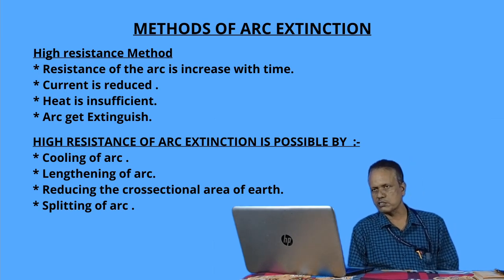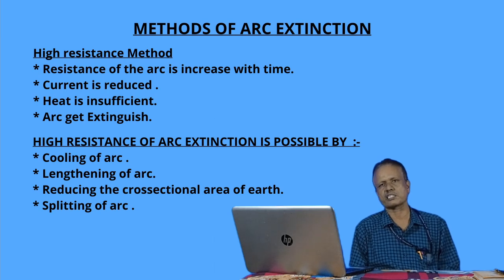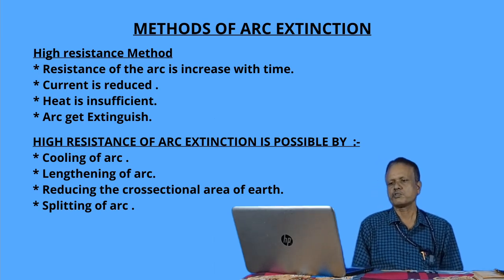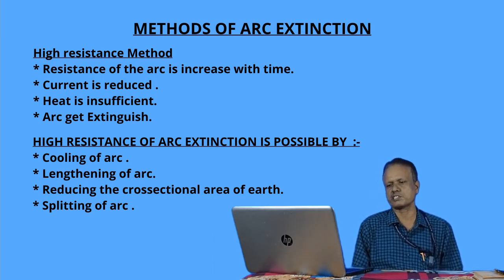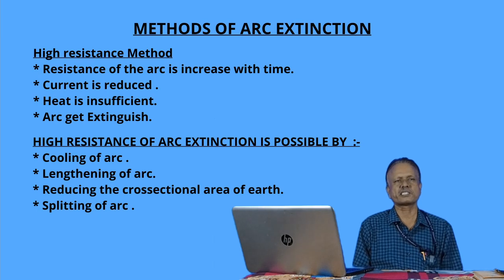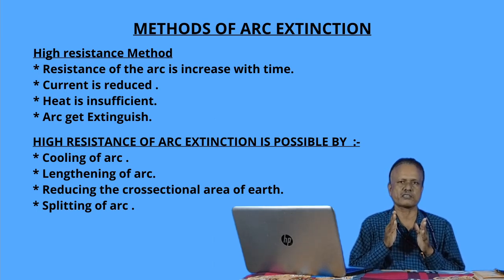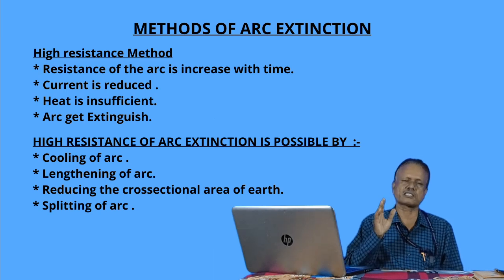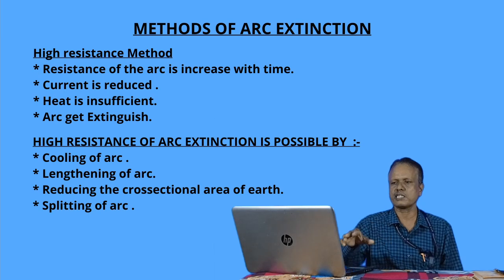Similarly, reducing the cross-sectional area of this arc. If we reduce the cross-sectional area of this arc, then also resistance is increased. Then the splitting of this arc. By splitting of this arc, if the arc is split into separate arcs, then its length is increased and it gets cooled. That is why the arc is extinguished.